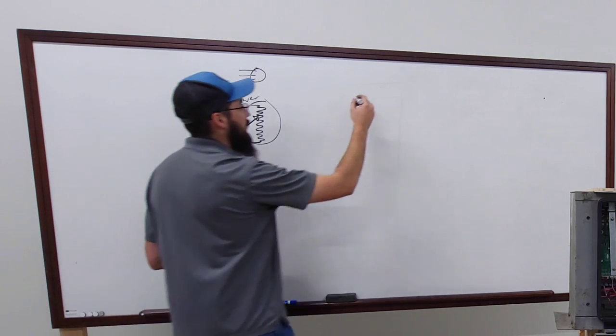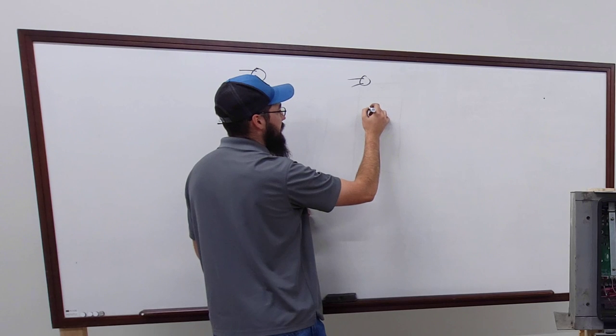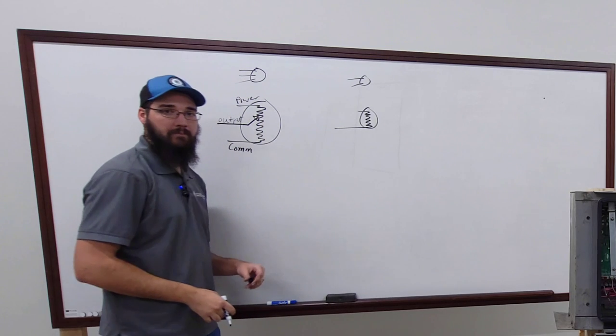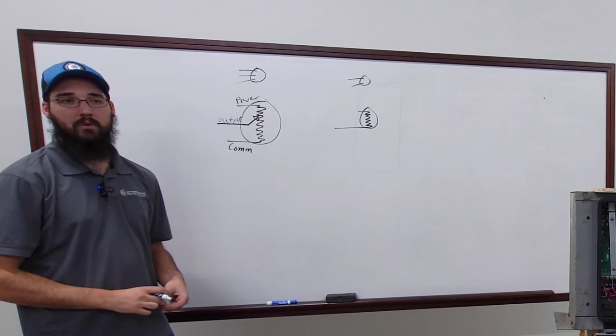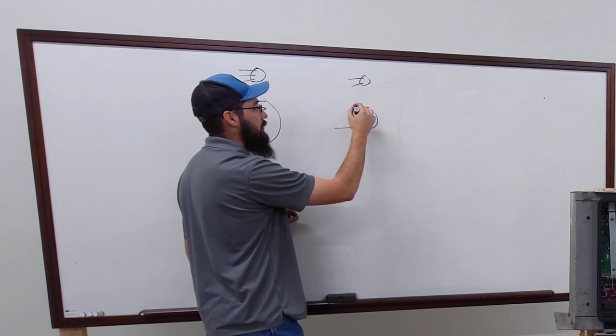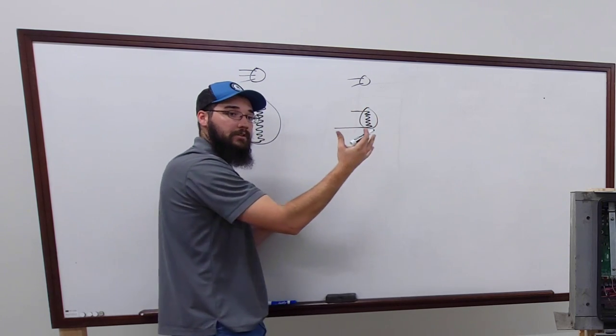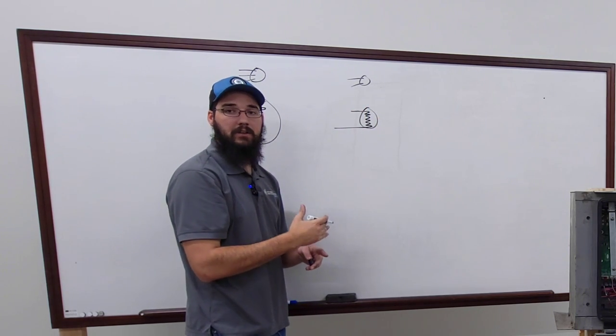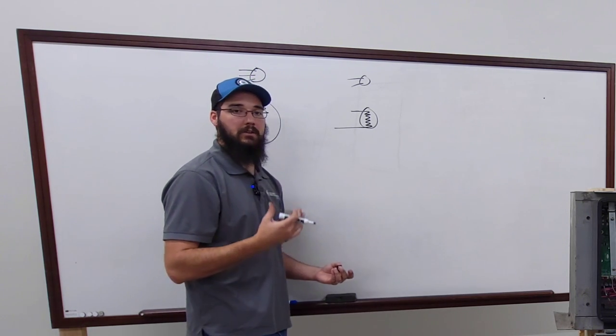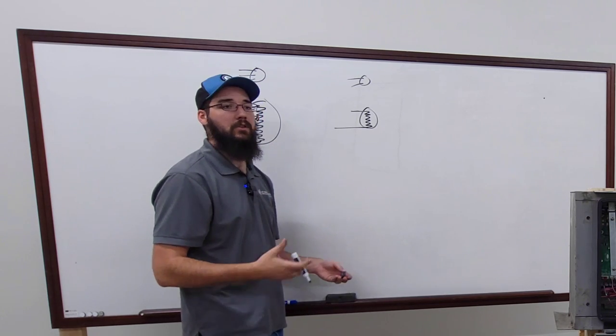Most of your thermistors are not directional — they're quite literally just ohms. They're a variable ohm device that's responsive to temperature. We can graph that response to make that ohm value mean a temperature. For example, Carrier is using a 5K at 77-degree thermistors. What that means is at 77 degrees, the thermistors on this panel are going to read 5,000 ohms, give or take a couple of percent.